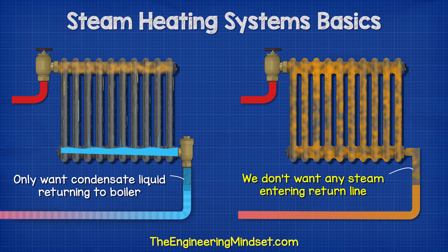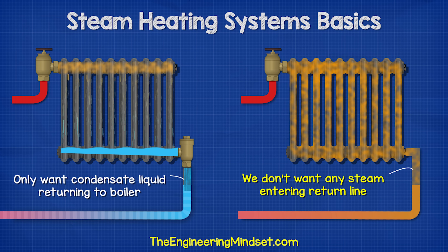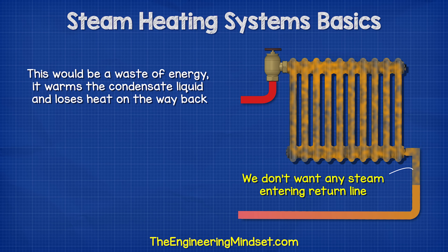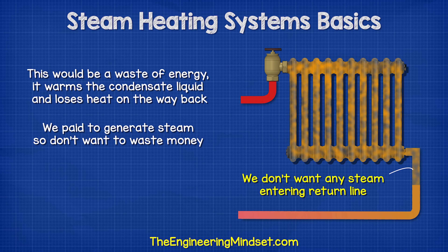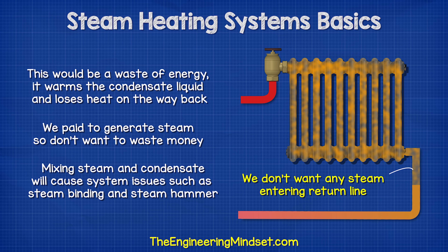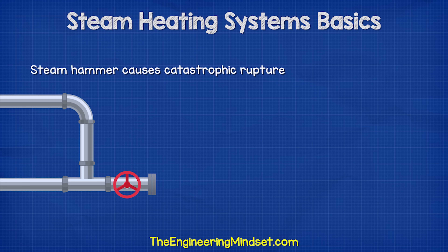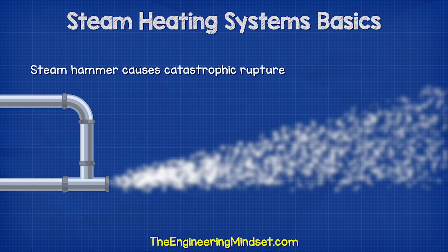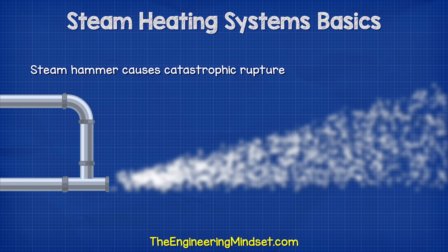We only want condensate liquid returning to the boiler. We don't want any steam getting into the return line. This would be a waste of energy, as it will warm the condensate liquid and also lose heat on the way back. We've paid to create the steam, so we don't want to waste it. Mixing the steam and the condensate will cause many problems for the system, such as steam binding and also steam hammer. This can be catastrophic for the system, so we must try to avoid this.